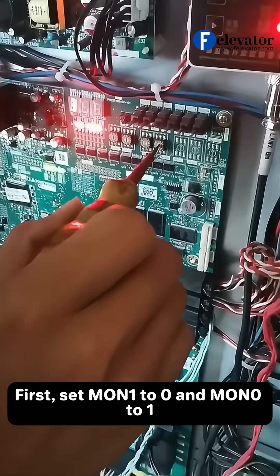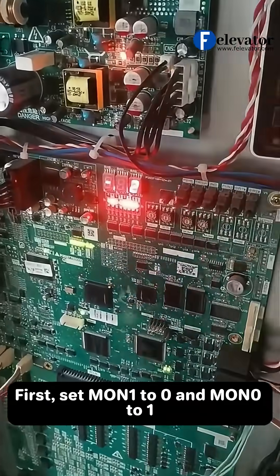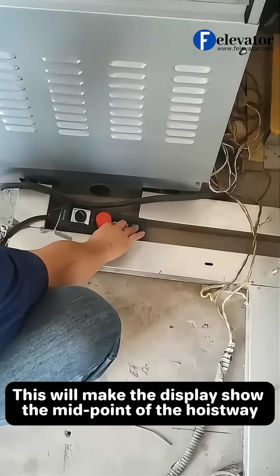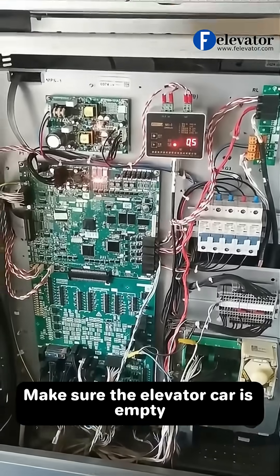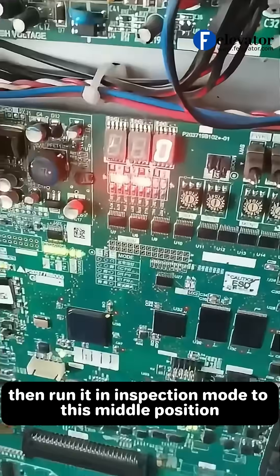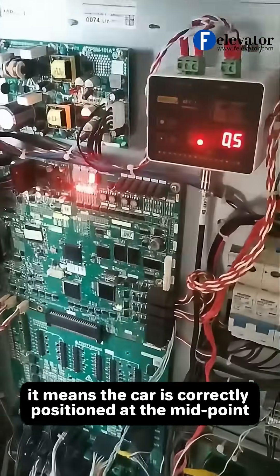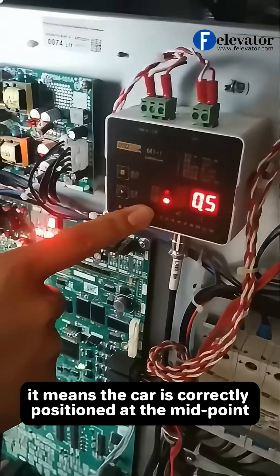First, set MON1 to 0 and MON0 to 1. This will make the display show the midpoint of the hoistway. Make sure the elevator car is empty, then run it in inspection mode to this middle position. When the display shows 0, it means the car is correctly positioned at the midpoint.